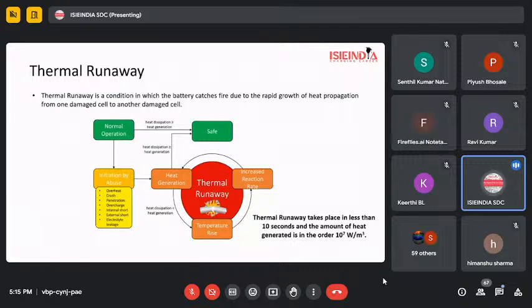This figure shows that if we do not have good heat dissipation, if we do not dissipate the heat produced in the battery, the temperature will rise, increasing the chemical reaction rate inside the battery pack, which causes more heat generation and further leads to thermal runaway. But if we dissipate heat greater than or equal to the heat generated, our battery pack will remain in normal condition and be safe.